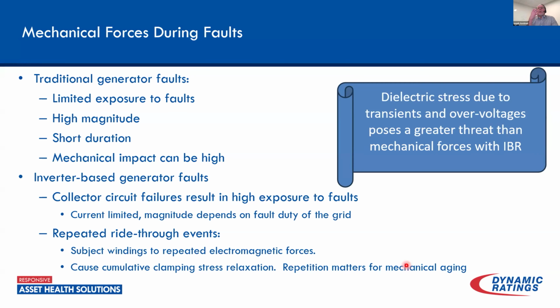Whereas when it comes to inverter-based transformers and inverter-based applications, dielectric stress due to transients, overvoltages, partial discharges, things like that are going to pose a much greater threat than what the mechanical forces do in inverter-based generation.